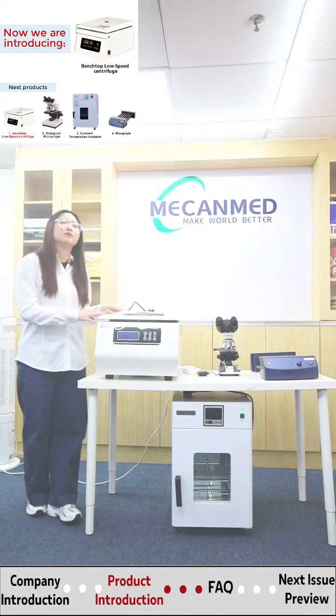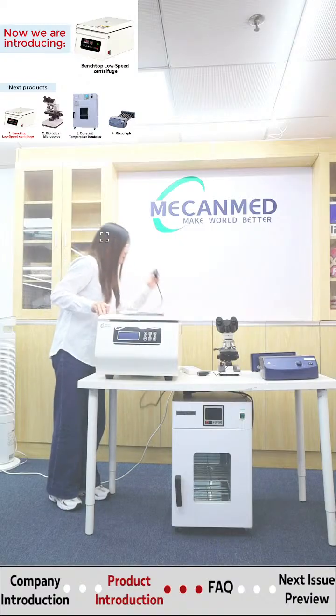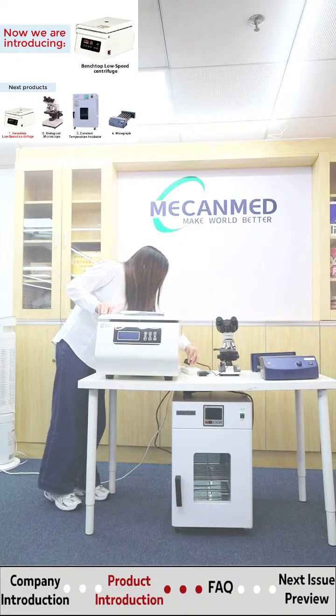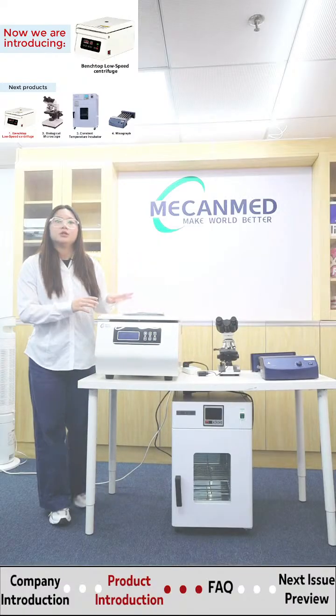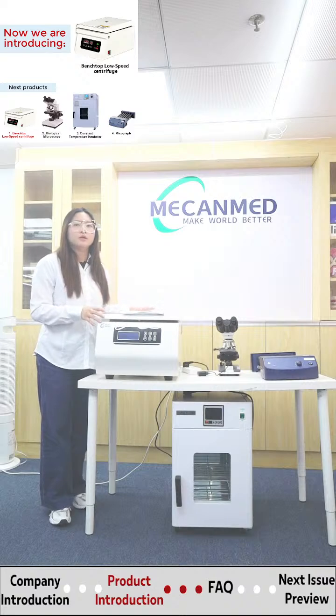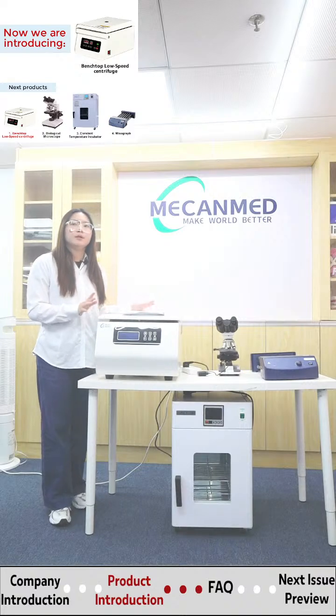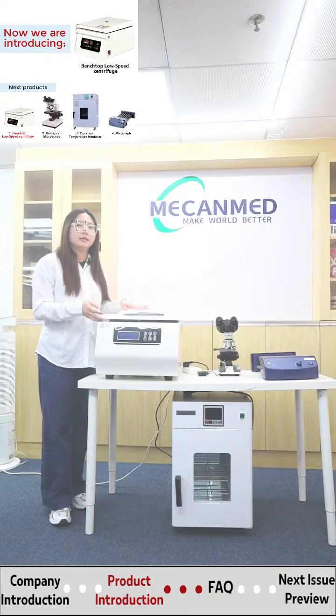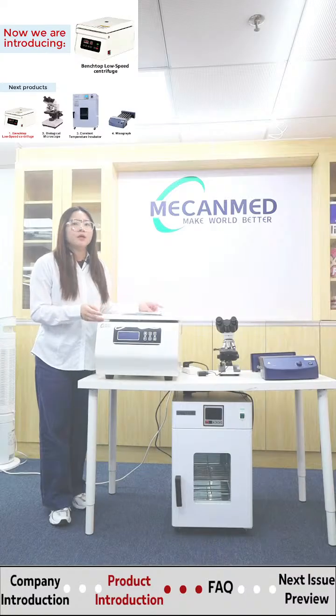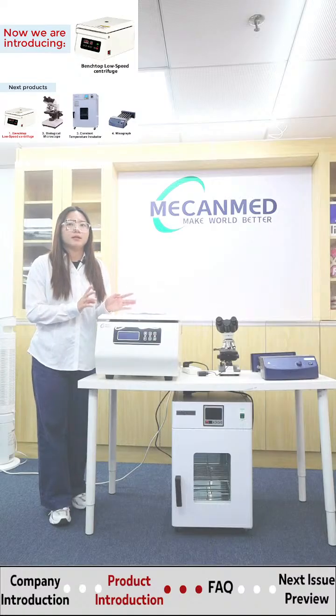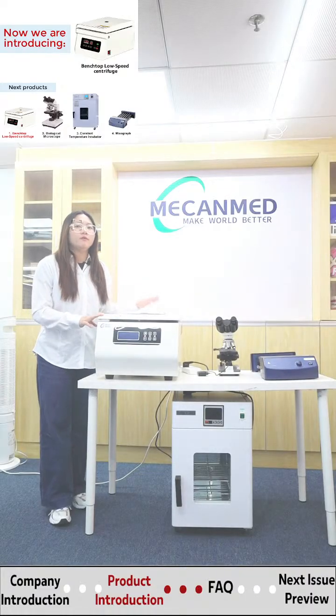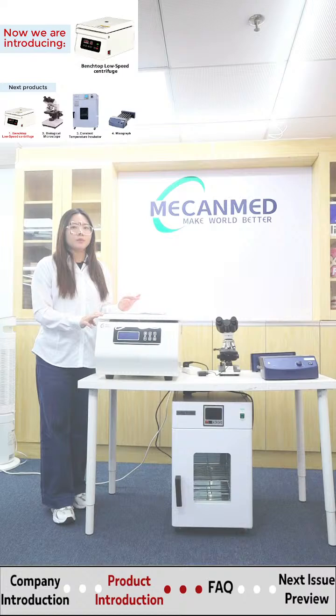First, connect the centrifuge lead to the power supply with the power cord. Next, open the centrifuge lid and rotor cover. Place the test tubes into the rotor. Make sure that samples in test tubes are properly balanced and place them opposite each other in the rotor, avoiding violent vibration or damage to the device. Then close the rotor cover and centrifuge lid.